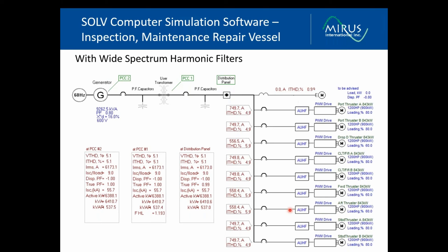We run the same simulation but with a passive filter on the front end. This filter then reduces the current distortion. You can see at each branch, overall current distortion at just over 5%, with voltage distortion just over 5% as well, well within the marine certifying standards.